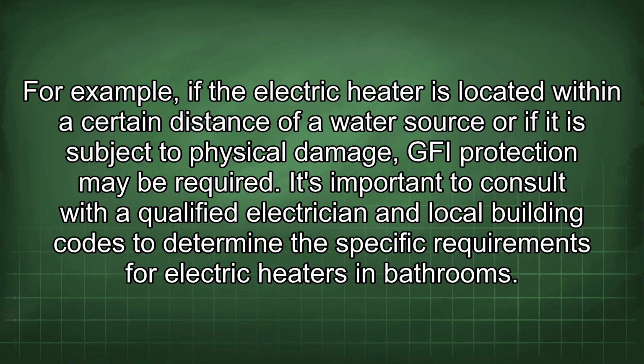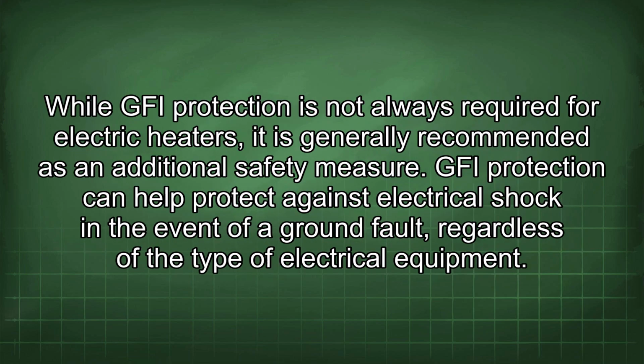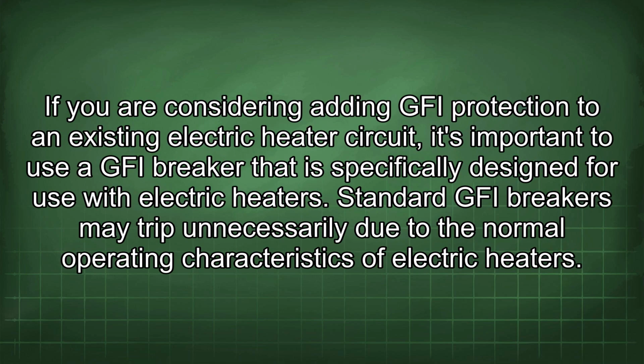It's important to consult with a qualified electrician and local building codes to determine the specific requirements for electric heaters in bathrooms. While GFI protection is not always required for electric heaters, it is generally recommended as an additional safety measure. GFI protection can help protect against electrical shock in the event of a ground fault, regardless of the type of electrical equipment. If you are considering adding GFI protection to an existing electric heater circuit, it's important to use a GFI breaker that is specifically designed for use with electric heaters. Standard GFI breakers may trip unnecessarily due to the normal operating characteristics of electric heaters.